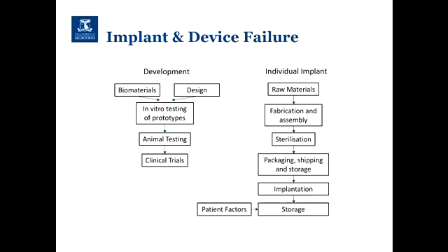Has it been implanted correctly? So sometimes it even comes down to the surgeon whether or not it fails. If it hasn't been implanted in the correct alignment, so the correct stresses are put on it, could that cause the device to fail? Has the implant or device to be implanted been damaged during the fabrication process?